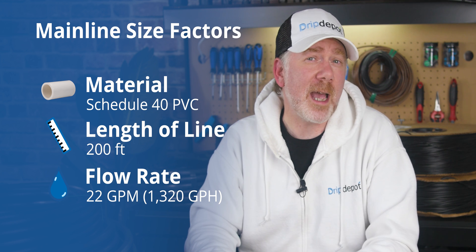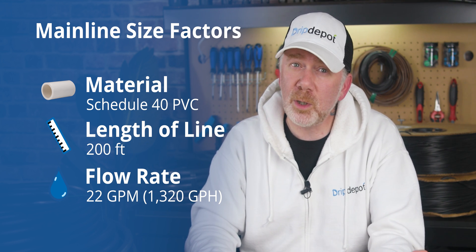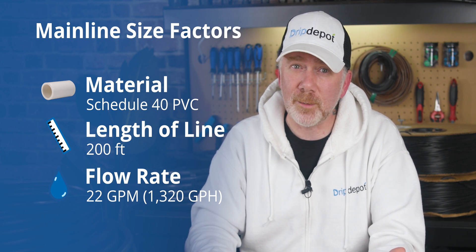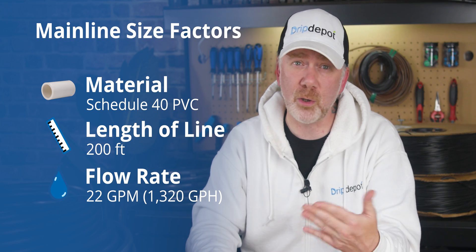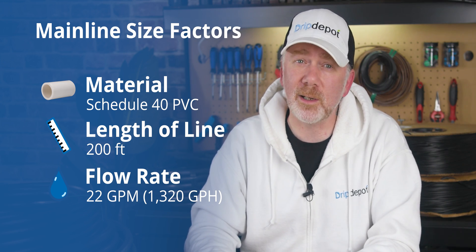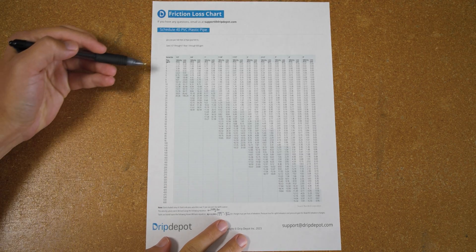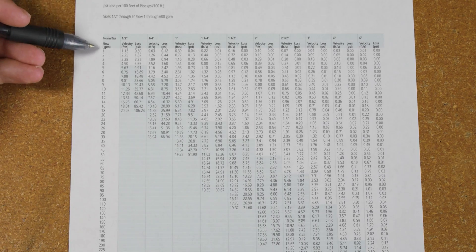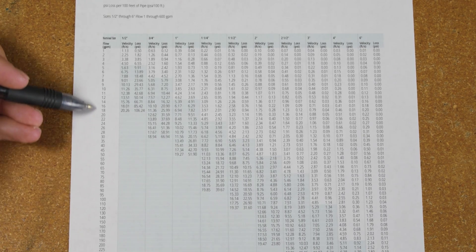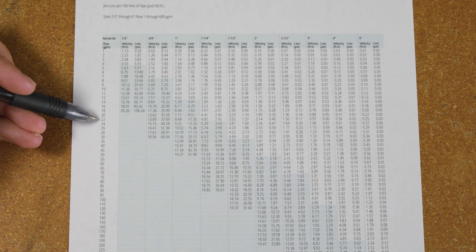The poly tubing calculator won't work here since we're going to be using PVC, and it's likely we'll need a diameter larger than one inch, which is the largest the calculator handles. To size our mainline here, we'll have to use the friction loss charts for PVC. Reading the charts is pretty straightforward: the rows are where you'll find your gallons per minute, and all you need to do is locate your system's flow rate — in this case, 22 gallons per minute.